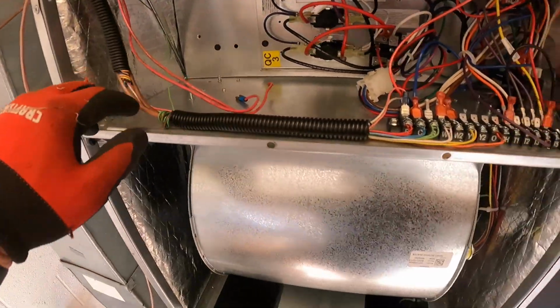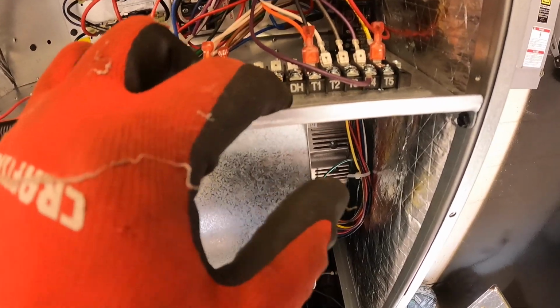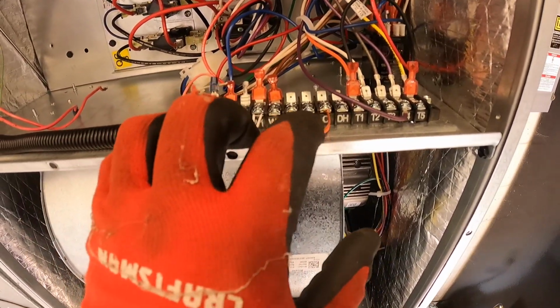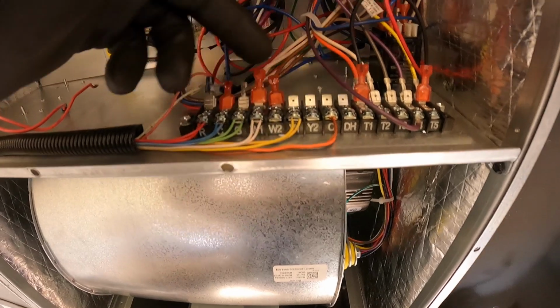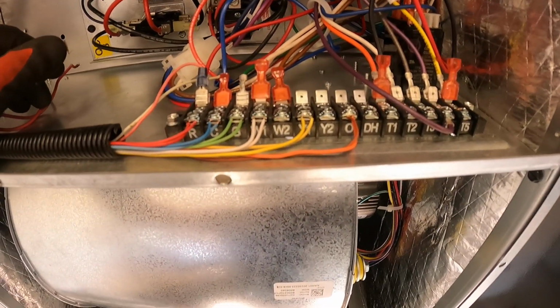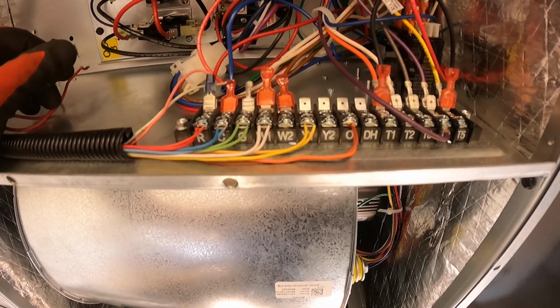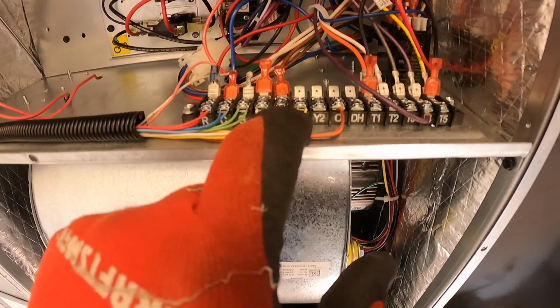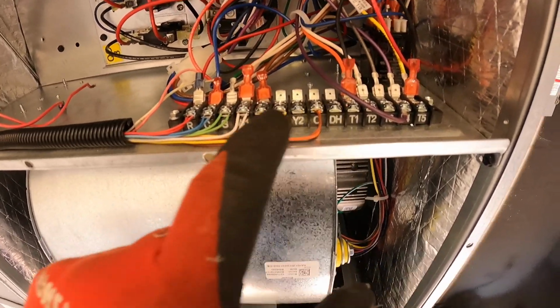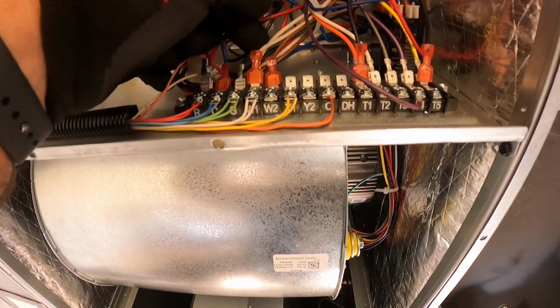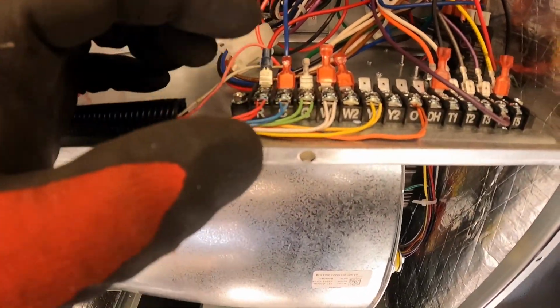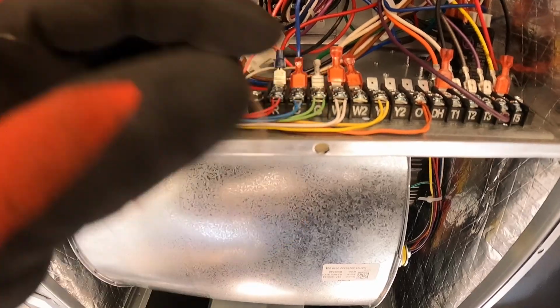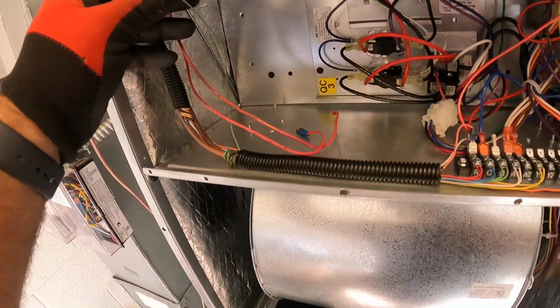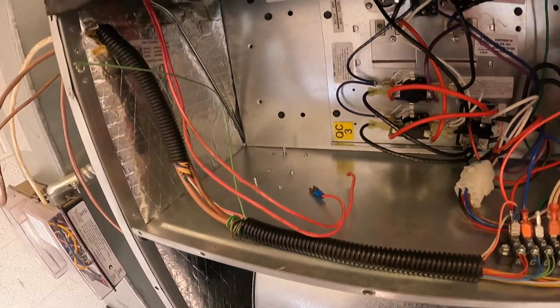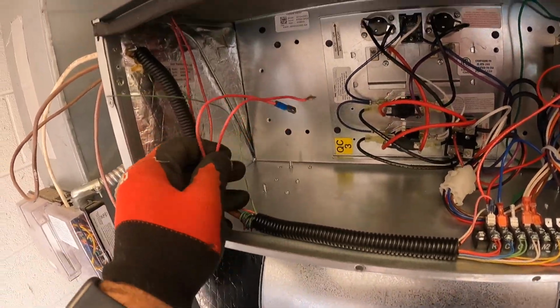Got the thermostat wires run in here and connected to the terminal strip. Of course, you wouldn't have to use the orange and the yellow since there's nothing on the other side, but it makes a good connection point - might be a good place to use your meter someday for troubleshooting. We've got our Y1 and our orange, there's our whites, which of course goes to the heater. Our greens - only have one green coming in, but I ran an extra green over here on this side in order to hook up this damper up there.